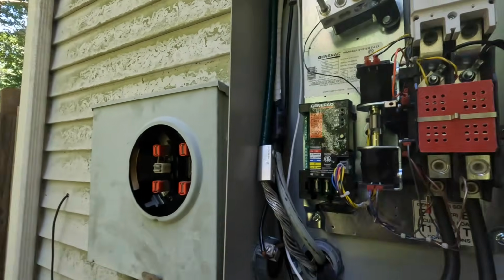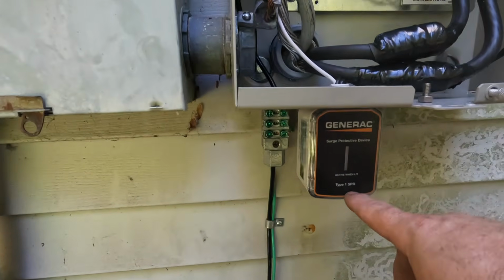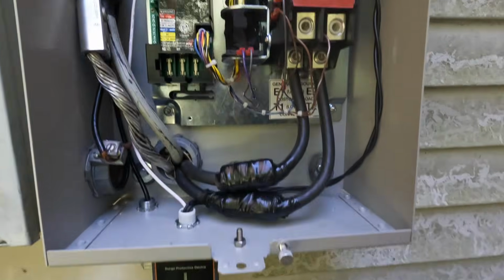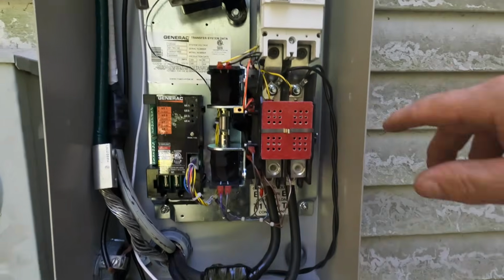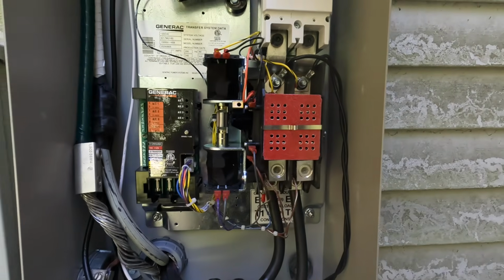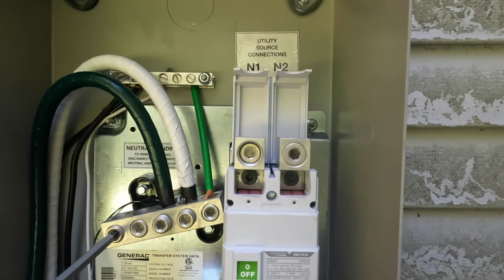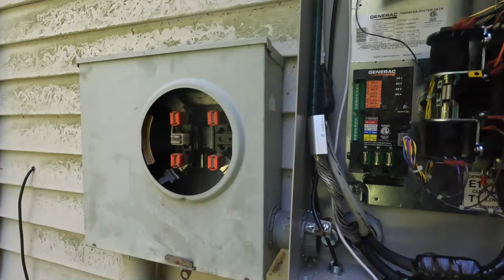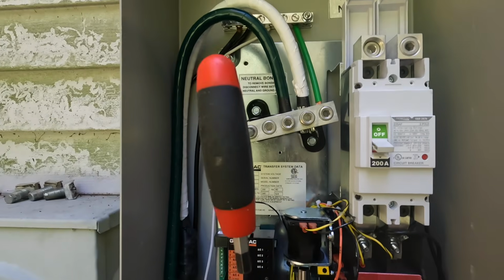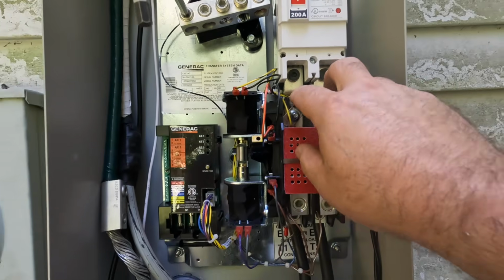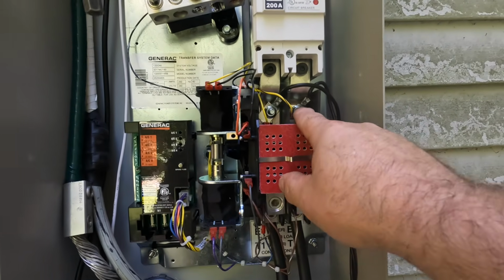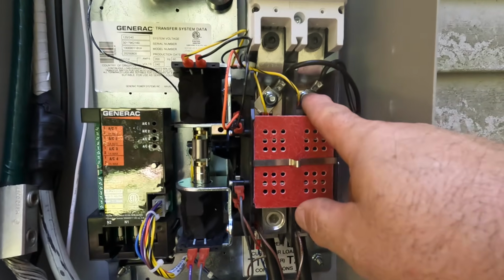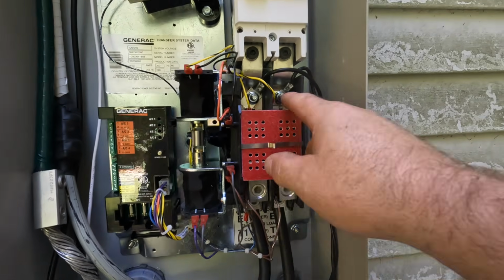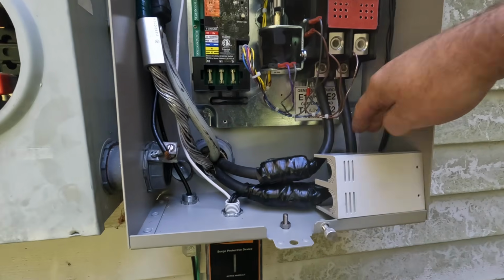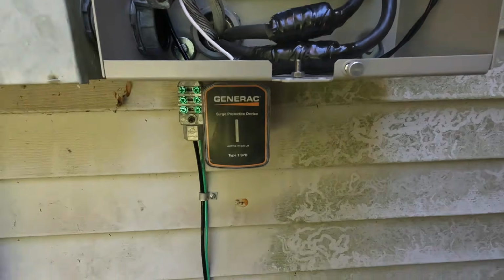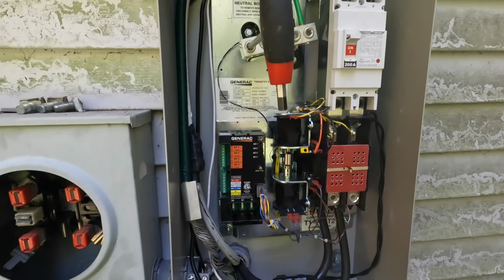Let me show you the connection. We have our type 1 surge protection device on the line side of the service panel, connected to these lugs. This is where the line side conductors from the meter will pass through. Right now it's off, but once turned on, these posts become energized at 240 volts between each other, 120 and 120. That's where we attached our surge protective device inside the automatic transfer switch by Generac.